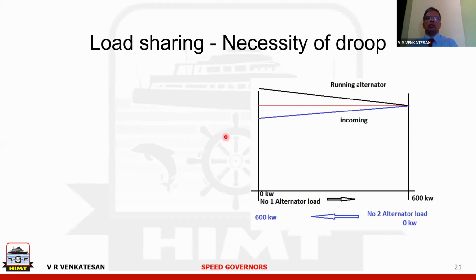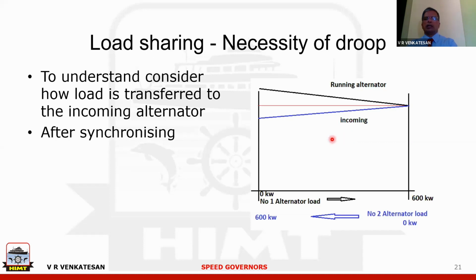Now you see how load is shared. The black line shows a running alternator. The current load is 600 kilowatt. Frequency is 60 hertz. It is running at 60 hertz and 600 kilowatt. So this point represents the present condition. Then what is done is you start the second generator, which is shown by the blue line. Second alternator is started. Its kilowatt is 0, not yet on load, and you synchronize it and close the circuit breaker here. So this point represents the closing of the circuit breaker.